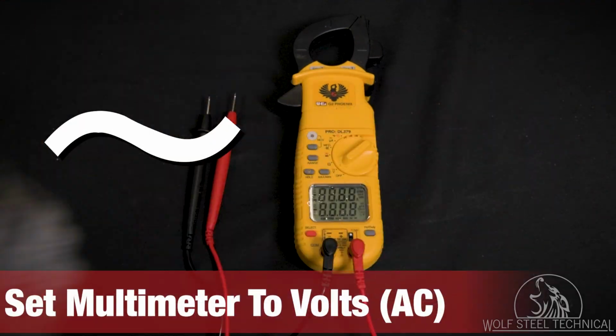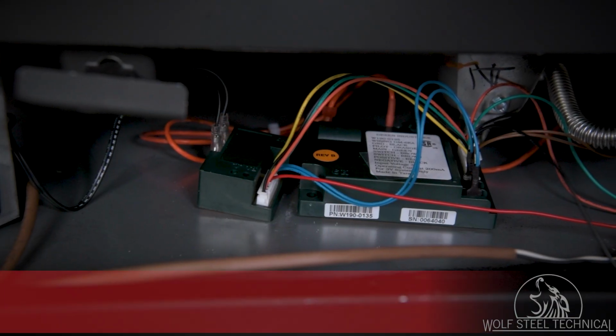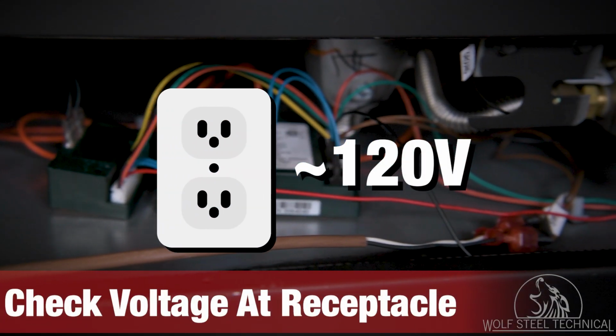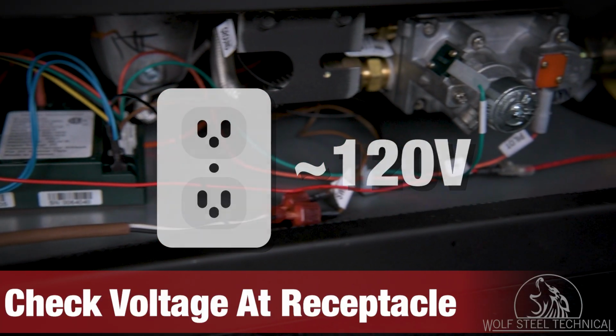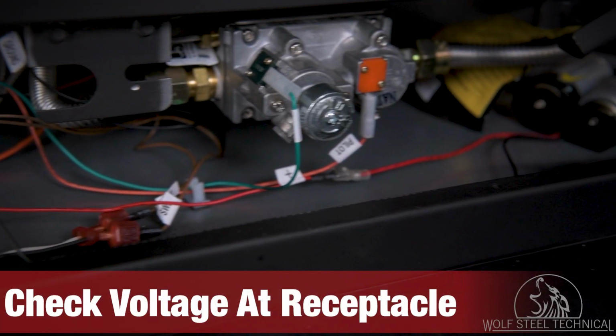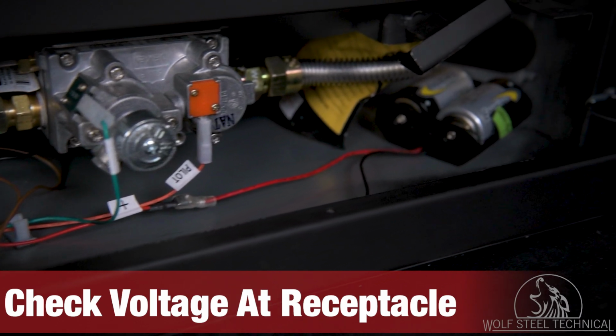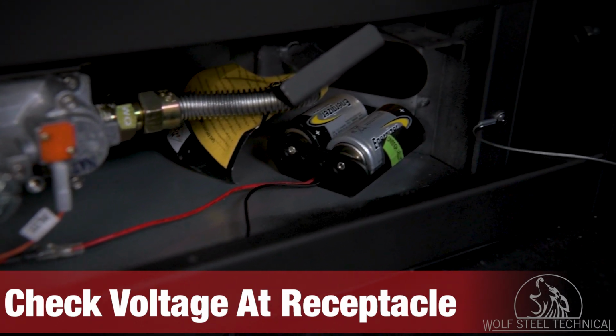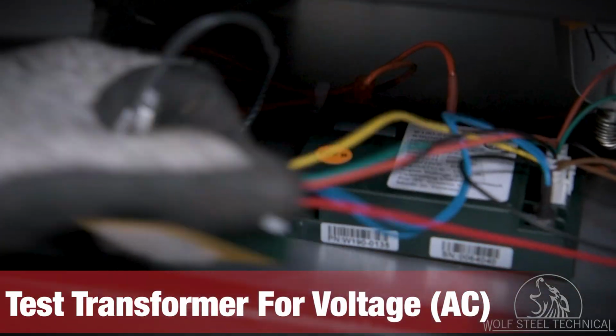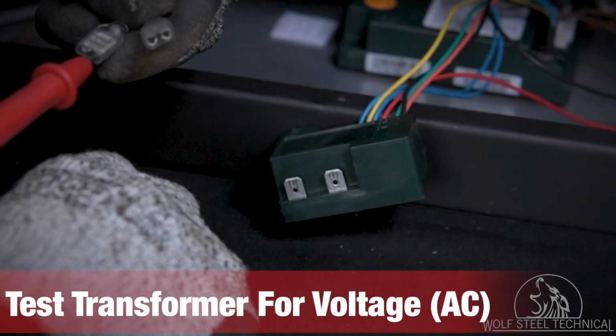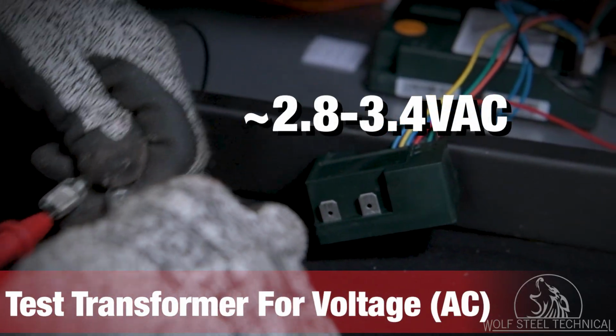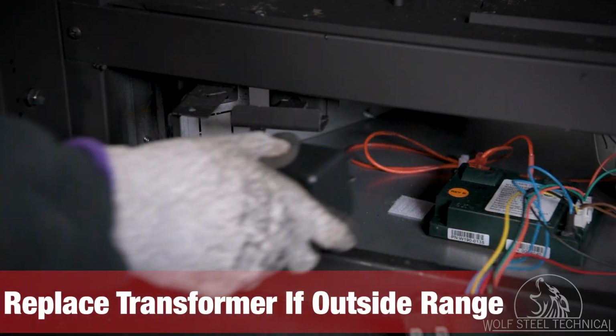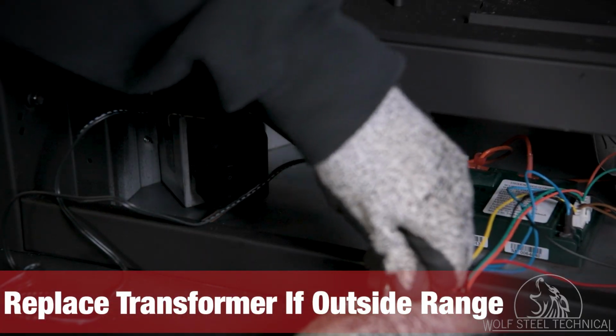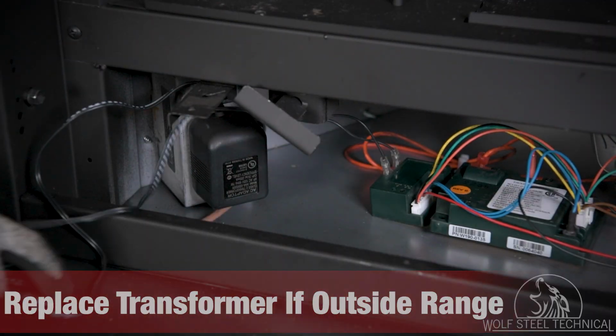Now set your multimeter to test for volts AC. Check for voltage at the receptacle to confirm that approximately 120 volts is being supplied to the unit. This is where the flow of electricity starts, as you track the movement of power through the unit and ensure all systems can operate correctly. Remove the battery relay from the control area and disconnect the transformer. Connect the multimeter leads to the transformer's spade connectors and test for approximately 2.8 to 3.4 volts AC. If voltage falls outside of this range and the supply has proven to be approximately 120 volts, then the transformer will need to be replaced.